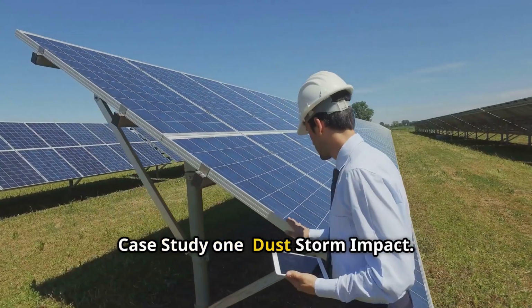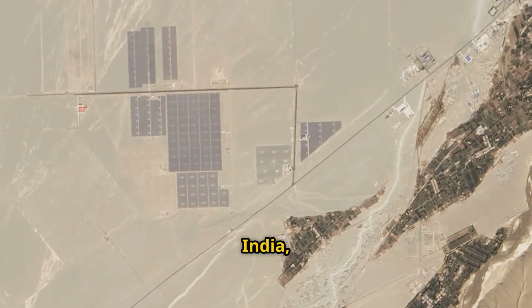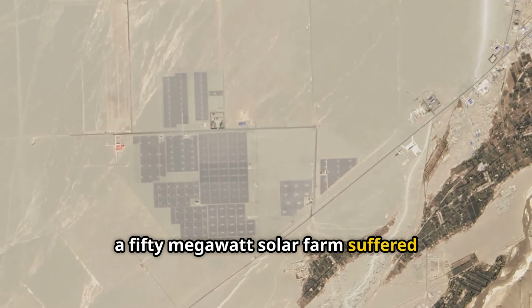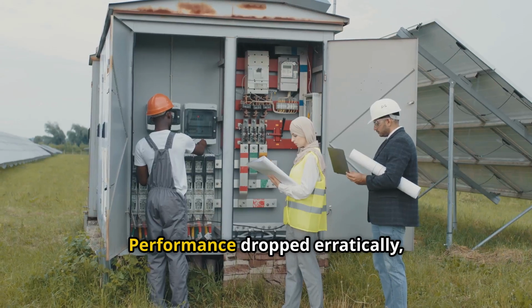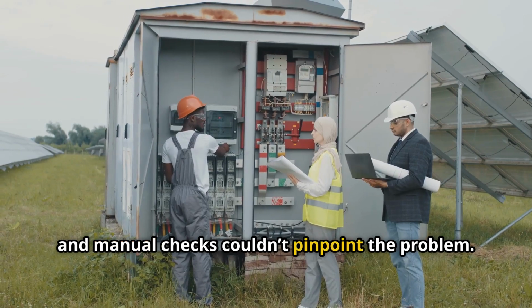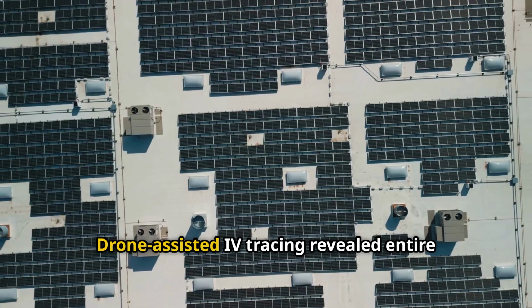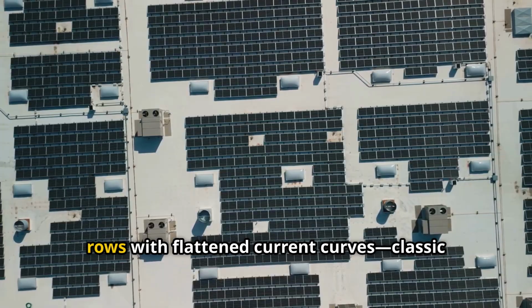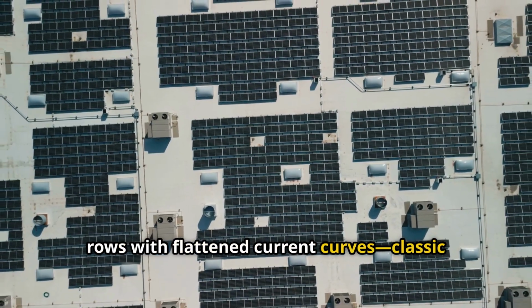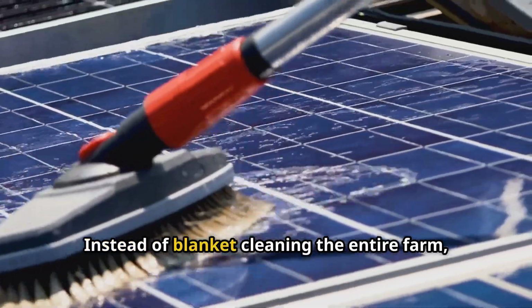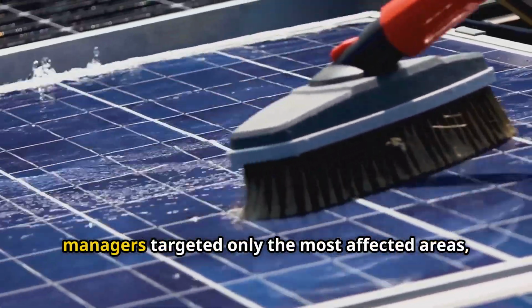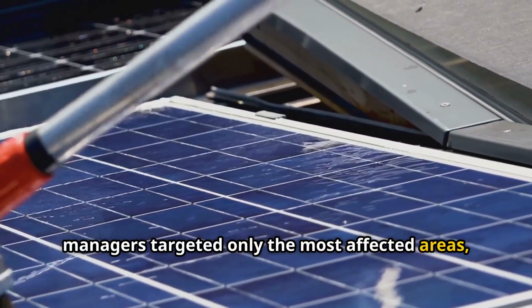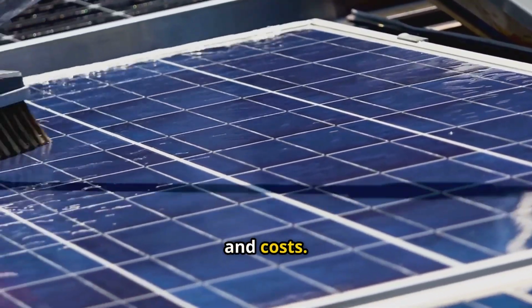Case study 1. Dust storm impact. In Rajasthan, India, a 50-megawatt solar farm suffered frequent dust storms. Performance dropped erratically and manual checks couldn't pinpoint the problem. Drone-assisted IV tracing revealed entire rows with flattened current curves, classic signs of soiling. Instead of blanket cleaning the entire farm, managers targeted only the most affected areas, saving water, labor, and costs.